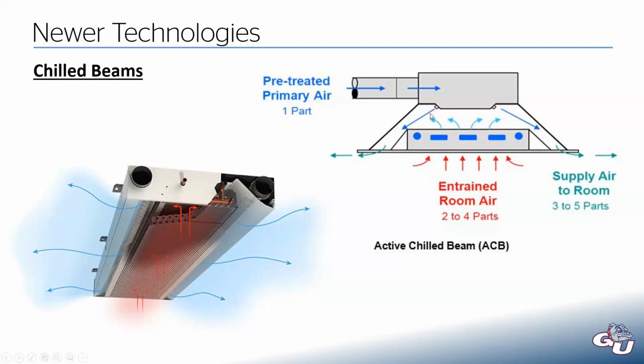And as it pulls the air here, that creates a vacuum below, which then pulls air in through the bottom. So you're getting about 1 part DOAS air that you're pushing through these nozzles, and then you get 2 to 4 parts of this return air. So overall, between those two, we're still moving a fair amount of air, but there's no fan inside this chilled beam. The only fan is what's moving this single part of primary air up at your DOAS unit. And this illustrates the thermal performance. You'll have the warm air getting pulled in through the center of the coil, and then the cold air gets pushed out the edges. I haven't designed a chilled beam system yet, but they're a rising technology right now.